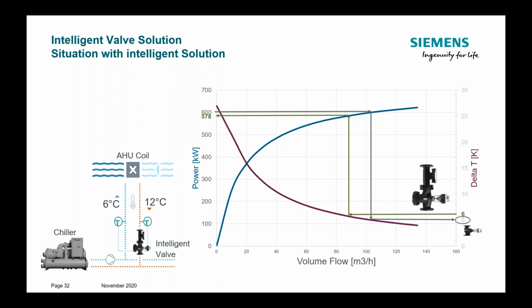So if the coil starts to get a weaker performance due to some dirt and dust in the coil, or if the airflow on the secondary side is reduced to a lower level due to a new situation in the building, it will react to this. So also over lifetime, this will always be an optimization to DeltaT and an optimization to maximum chiller efficiency and lowest possible volume flow in the system in each and any solution.